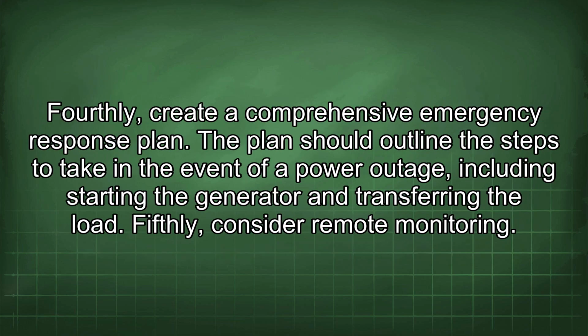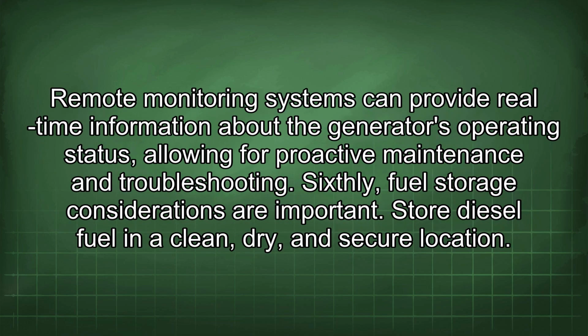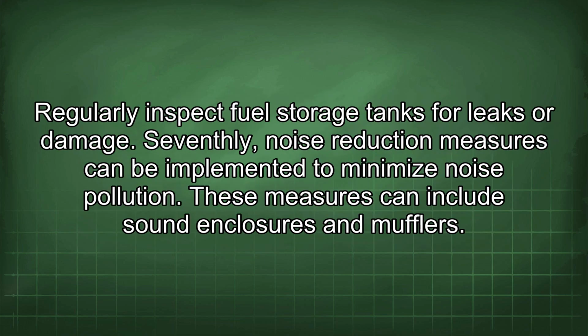Fourthly, create a comprehensive emergency response plan. The plan should outline the steps to take in the event of a power outage, including starting the generator and transferring the load. Fifthly, consider remote monitoring. Remote monitoring systems can provide real-time information about the generator's operating status, allowing for proactive maintenance and troubleshooting. Sixthly, fuel storage considerations are important. Store diesel fuel in a clean, dry, and secure location. Regularly inspect fuel storage tanks for leaks or damage.